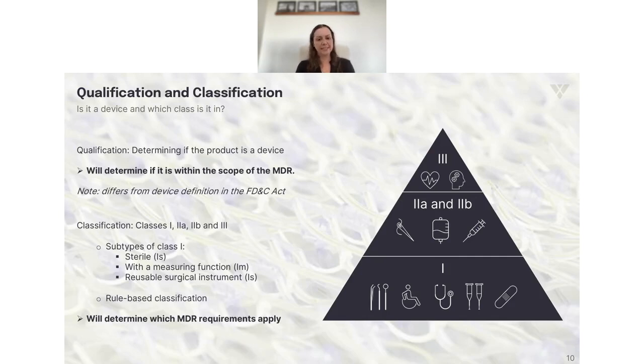So an overview of qualification and classification. Essentially, it is to answer the question: is it a device, and which class is it in? So qualification, then, is the product a device, which will essentially determine if it's within the scope of the MDR. Now note here that it's not just a device that's in the scope of the MDR. There is now an annex to the MDR of devices without a medical purpose that are to be treated as devices. You can also have other types of products which are accessories to medical devices, which then place it within the scope of the MDR.